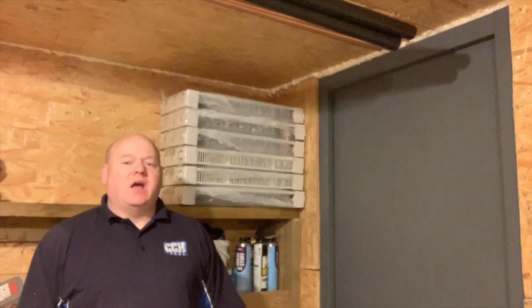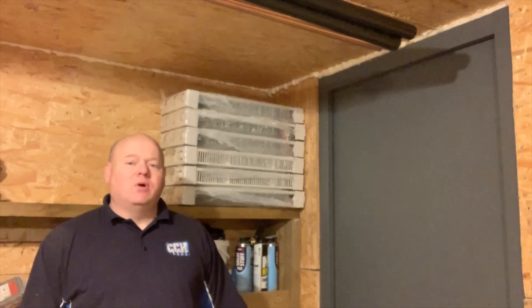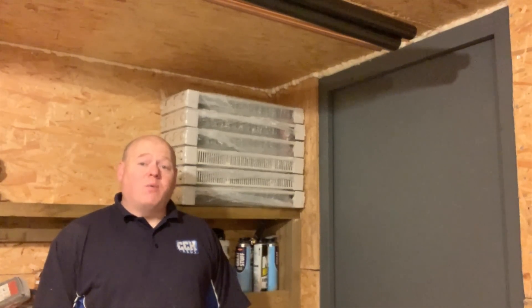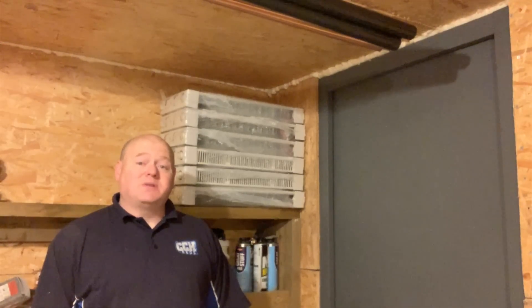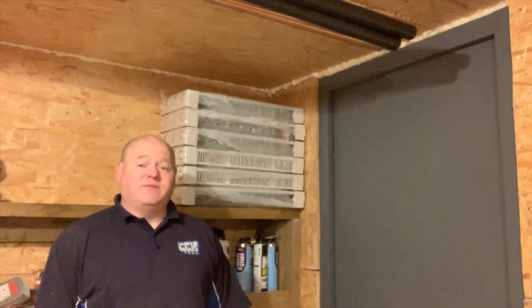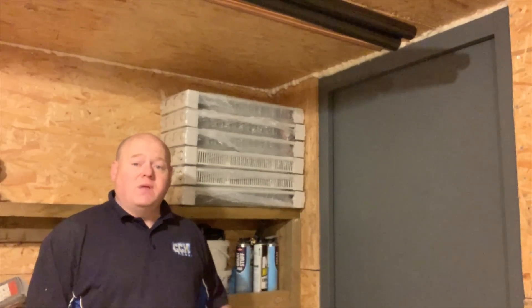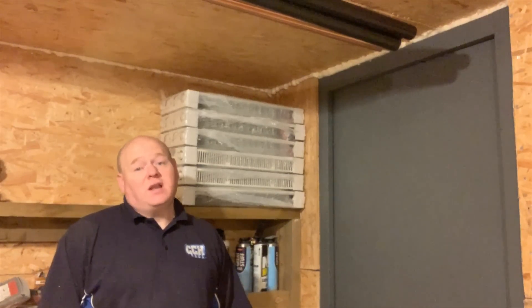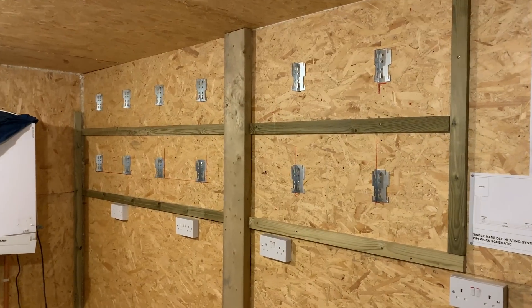My name is Alan Hart, and today I wanted to pipe a central heating system up. I'm going to pipe this as a one-pipe system. Nowadays we wouldn't install one-pipe systems, but this is to show you what a one-pipe system would look like, and also if you ever need to go to a system and adapt it and it's a one-pipe system. I'd like to thank Trade Help for supporting this video — they paid for the radiators, the pipe, and everything so that I could do this video.